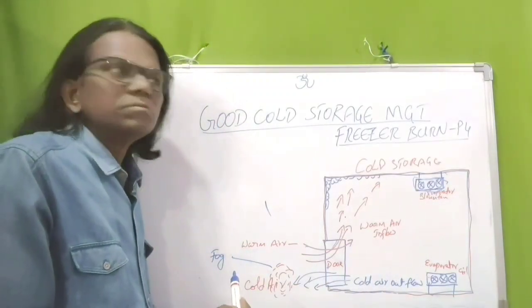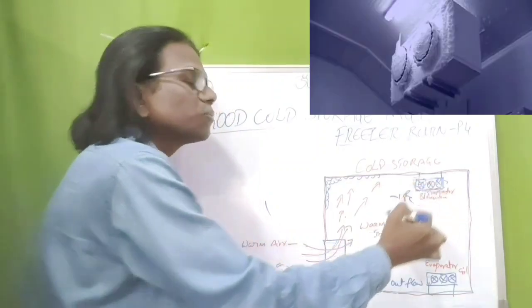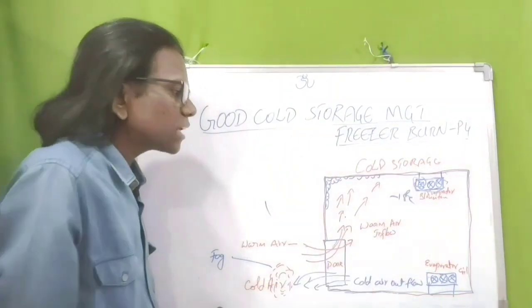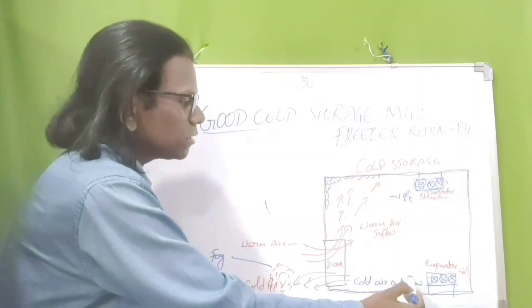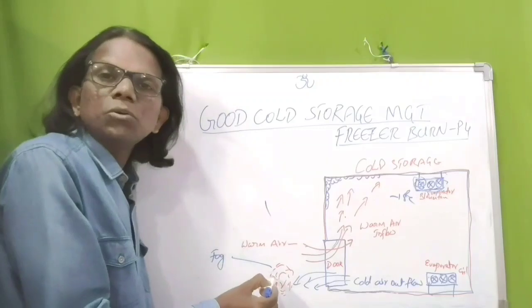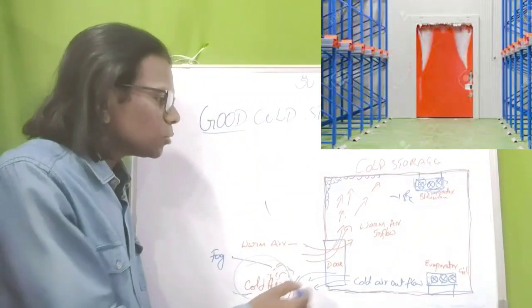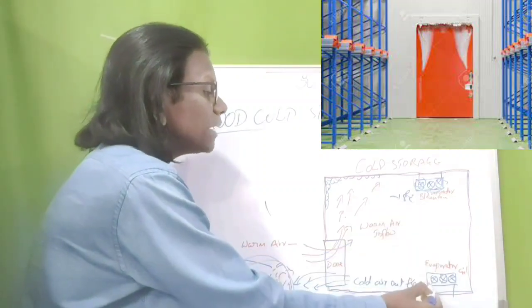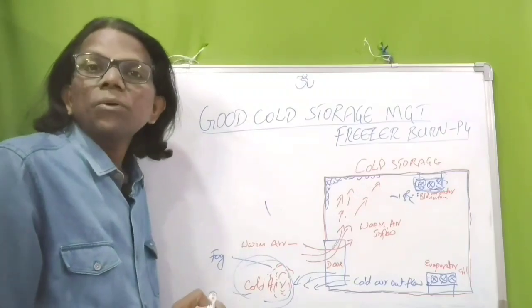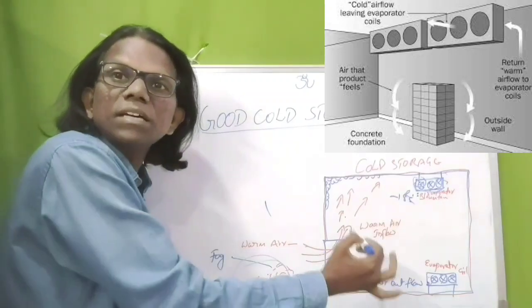If the cold storage is running at minus 18 to minus 10 degrees and ice forms on the cooling coils, the fans circulating the air cause the temperature to drop drastically. Cold air always comes down and moves out, so at the opening door of the cold storage you can see fog or mist. This is how the cold store mechanism works, and the blower velocity — the speed of air circulation — also influences product dehydration. The velocity should match the size and design of the cold storage.